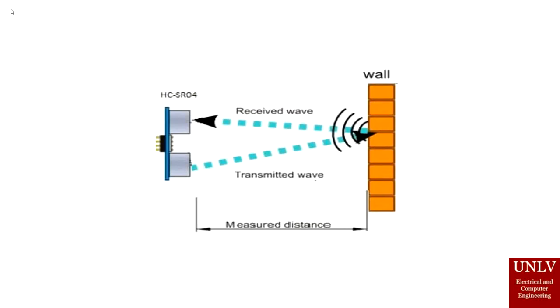To calculate the distance from the sensor to the tank, we use the time taken for the wave to leave and return to the device, multiplied by the speed of sound and divided by 2. We divide by 2 because we only need to know the distance between the sensor and the surface, instead of the full distance travelled by the wave.